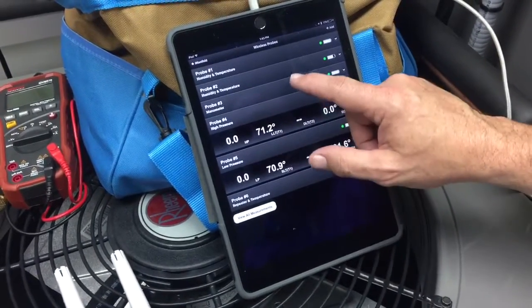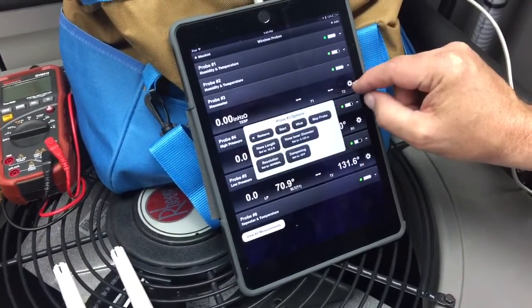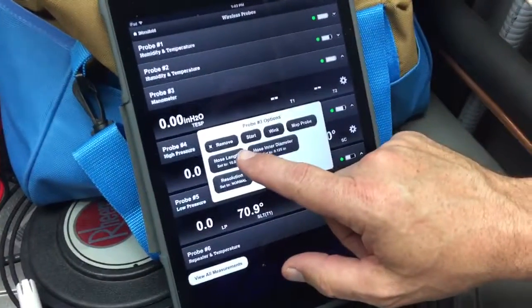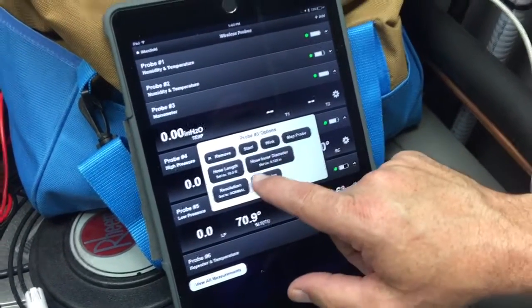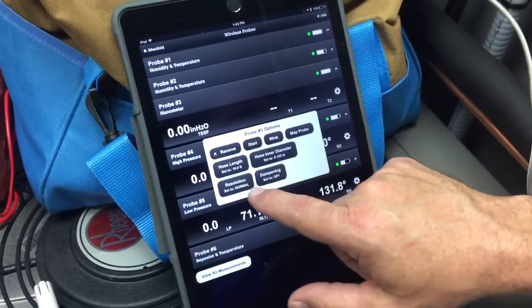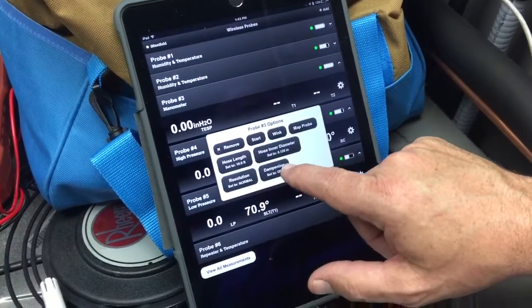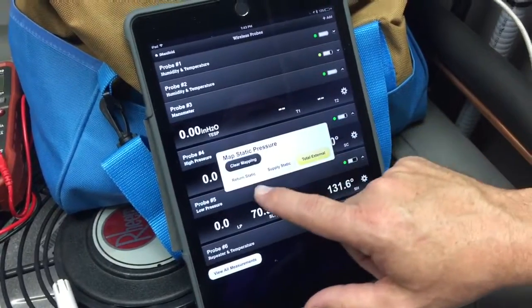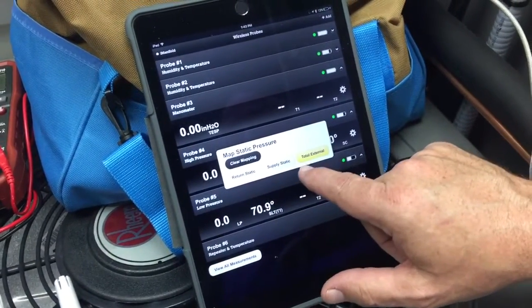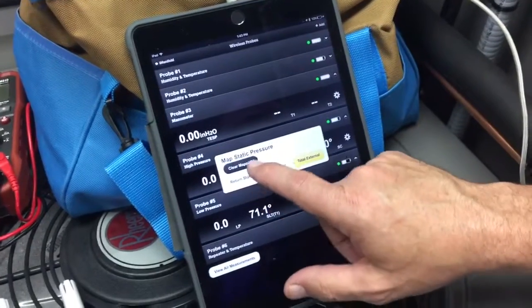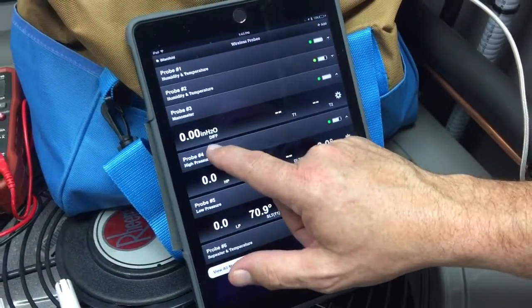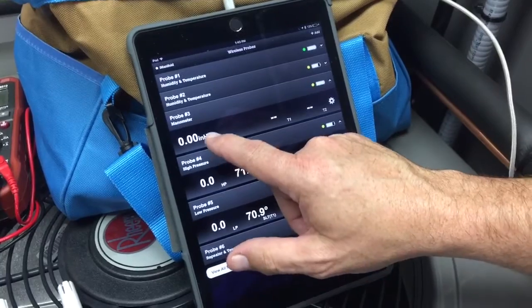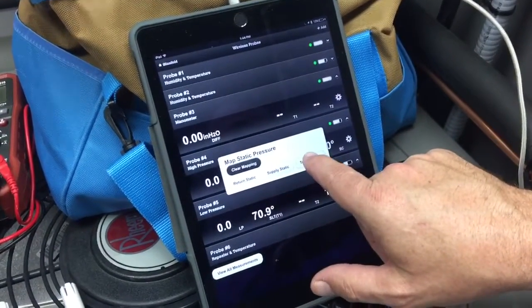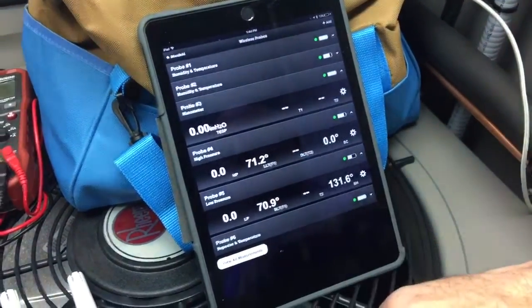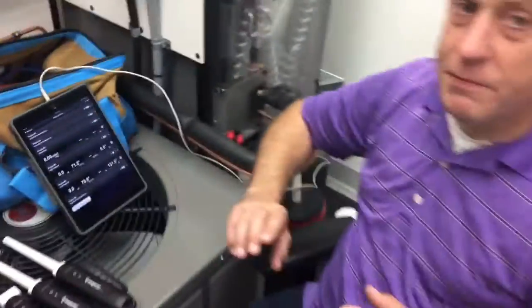Things like our manometer, if we open the manometer up, have a much deeper level of configuration where not only can we remove the probe or map the probe, but we can also set the hose length, the inner hose diameter, the resolution, and dampening on the probe. If we want to map this probe and change its function to return or supply or total external, we can actually do that. If we clear the mapping out altogether, it's just going to go to differential pressure, right? So if I want that to measure total external, I just tap on total external and it's going to hold that.